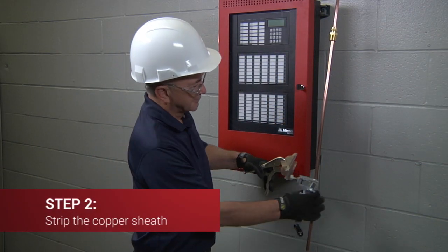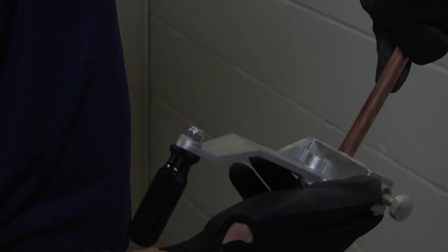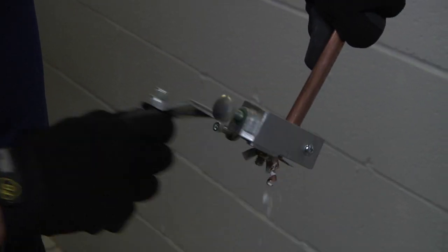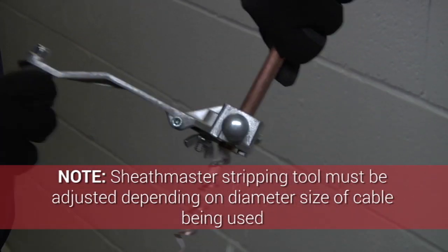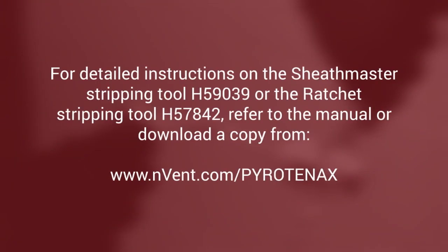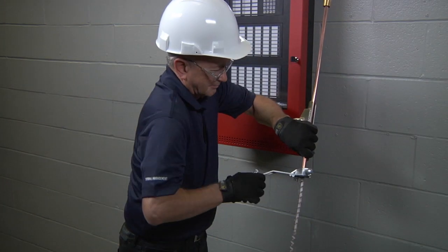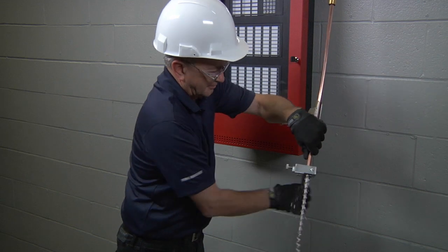Next, strip the copper sheath off the MI cable. Gripping the cable with the hand vise and using the stripping tool, begin stripping the copper sheath back towards the first mark. Note that the sheath master stripping tool must be adjusted depending on the diameter size of the cable being used. For detailed instructions on how to operate the sheath master stripping tool or the ratchet stripping tool, please refer to the instruction manual that came with the tool or download a copy from nvent.com/Pyrotenax. Continue to strip the copper sheath, adjusting the grip on the hand vise as you move up the cable to keep it from twisting.